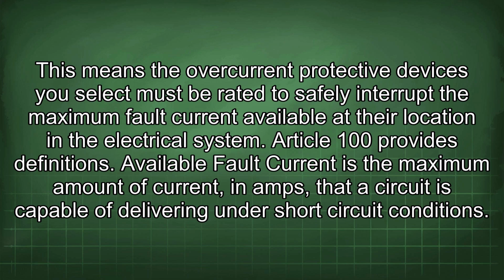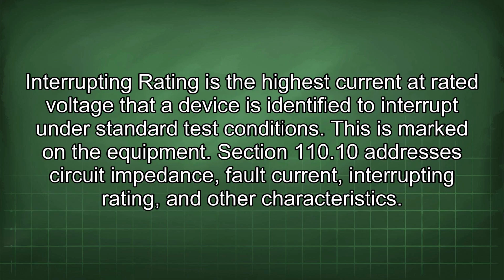Article 100 provides definitions. Available fault current is the maximum amount of current, in amps, that a circuit is capable of delivering under short-circuit conditions. Interrupting rating is the highest current at rated voltage that a device is identified to interrupt under standard test conditions. This is marked on the equipment. Section 110.10 addresses circuit impedance, fault current, interrupting rating, and other characteristics.